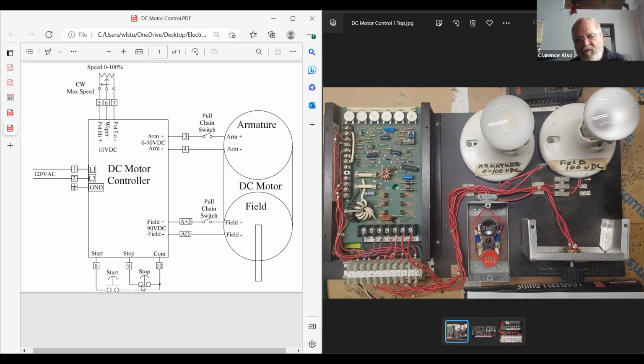We're going to prove to ourselves that this stop-start switch works, but we've got to isolate it, which means we've got to take a wire off. What wire would you guys take off if we were going to isolate the stop and the start and do some testing? What would you do, how would you isolate it? I'd take off wire 8 and 10. What if I told you it's a lot easier to pick out if you just do one?